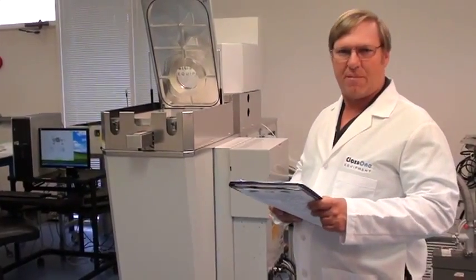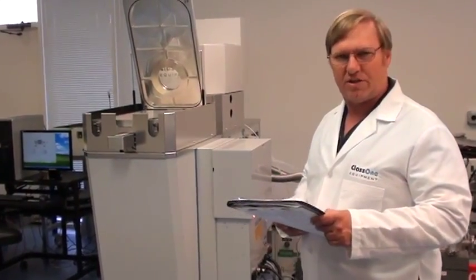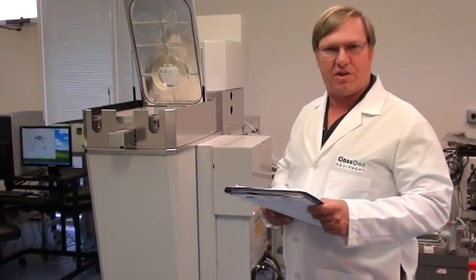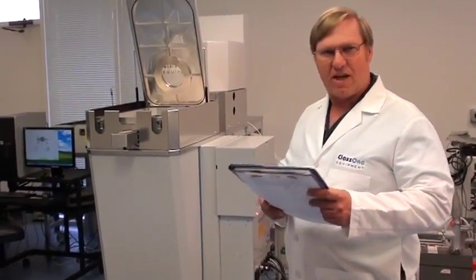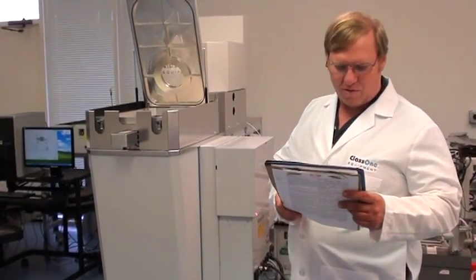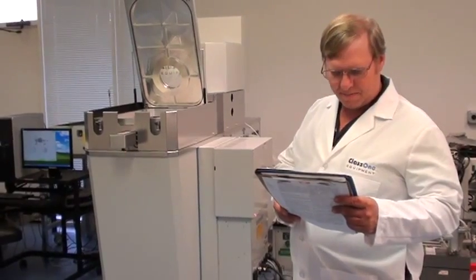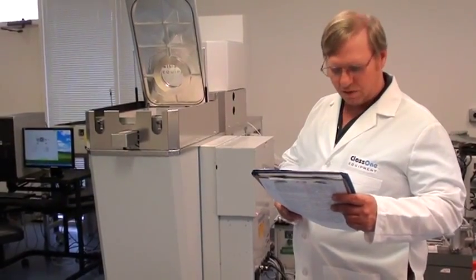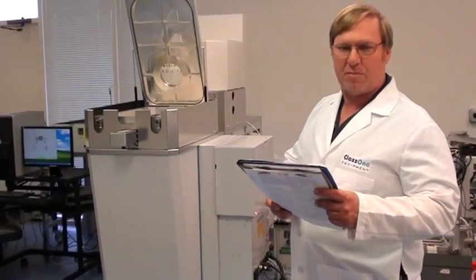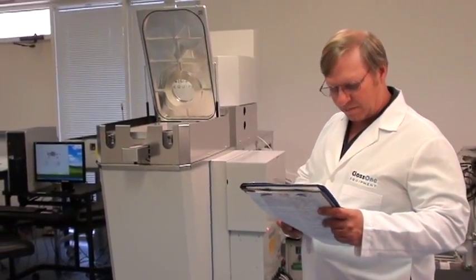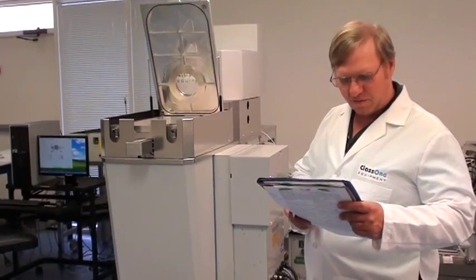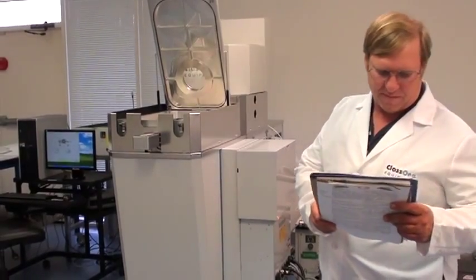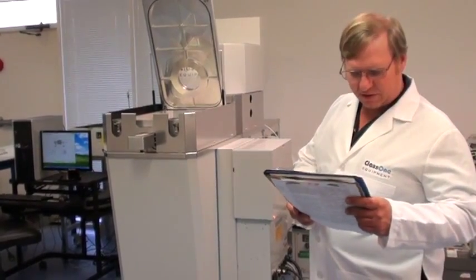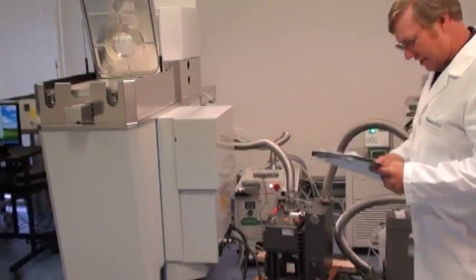The electrode is cooled down to -5 degrees Celsius. Chamber and load lock walls are heated up to 60 degrees. It has an Alcatel maglev turbo, ATH 1300M with a 1300M controller. Advanced Energy RF power supply. A brand new HP computer with brand new software from Oxford. Runs PC 2000 version 1.8 software. New monitor, keyboard, mouse.